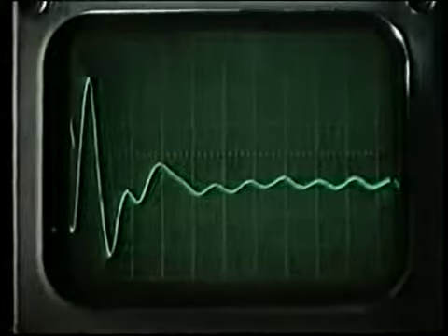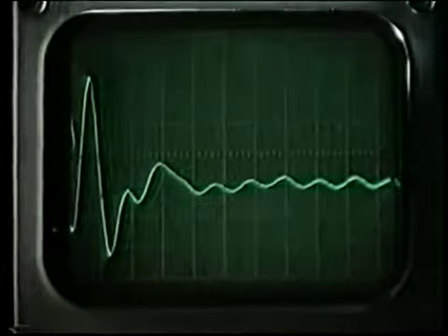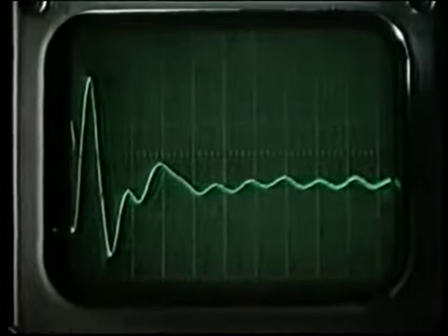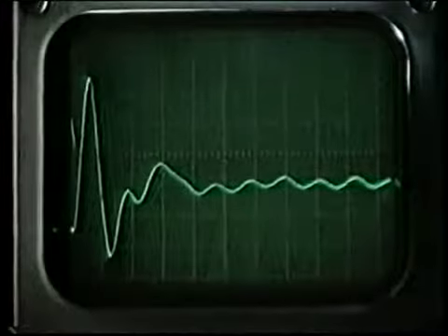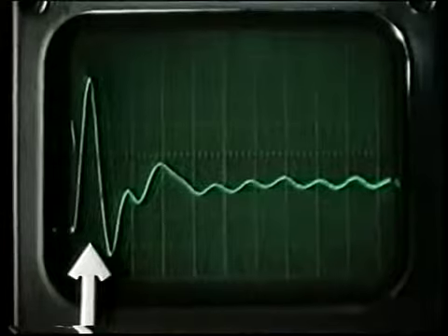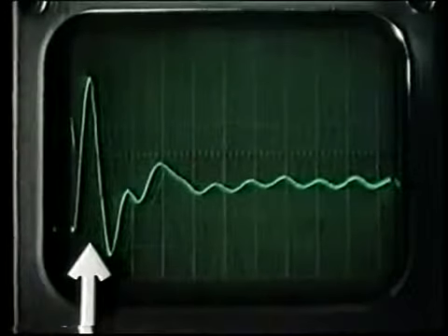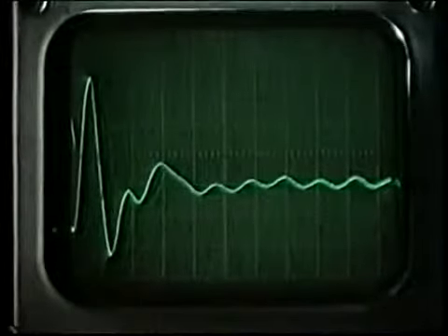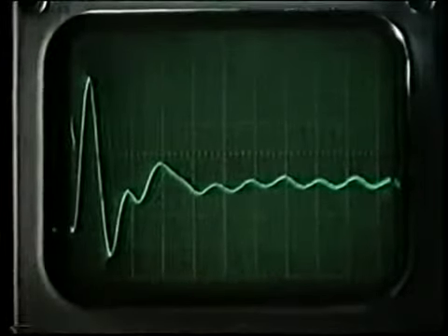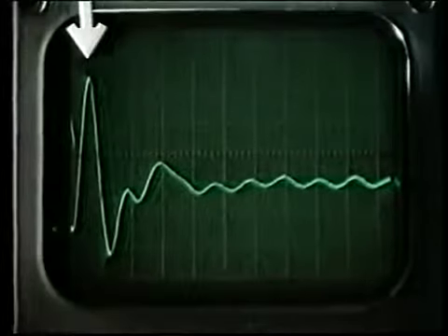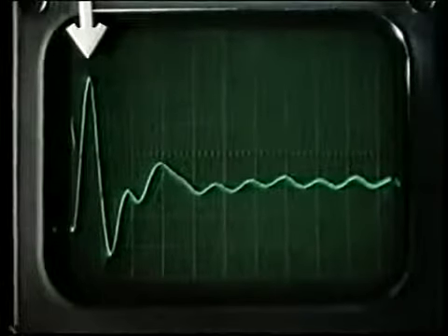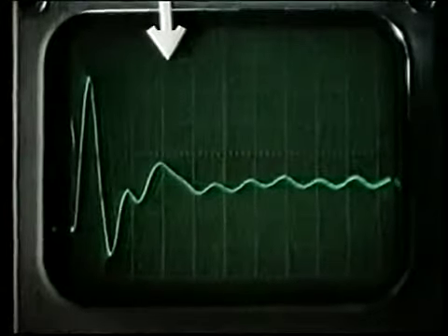Along the horizontal axis, we're plotting out the separation between the two mirrors, and along the vertical axis, the reading on our detector. In fact, the whole trace would be symmetrical about the zero path separation, which is located in this region here, but we're only displaying half the trace for clarity. The rest of it would be off to the left. Well, as we might expect, there's a good, strong signal at zero path separation, zero path difference, and quite a bit of information going way on out here.